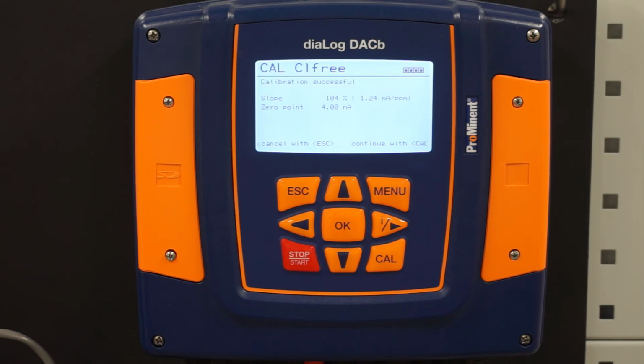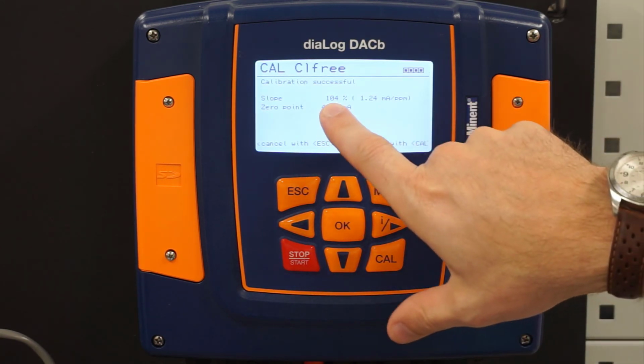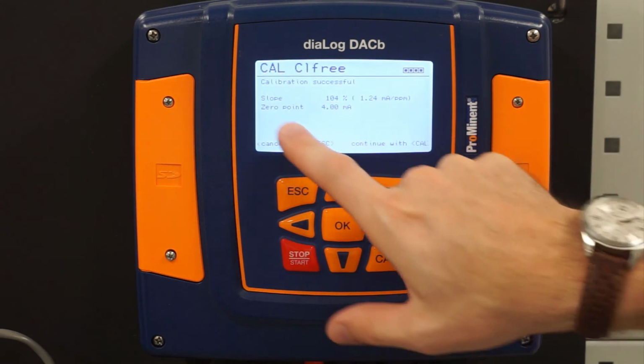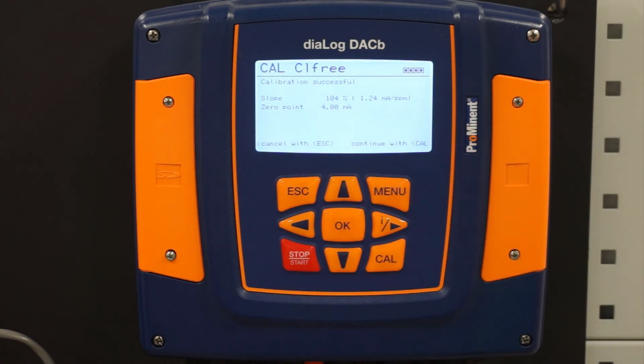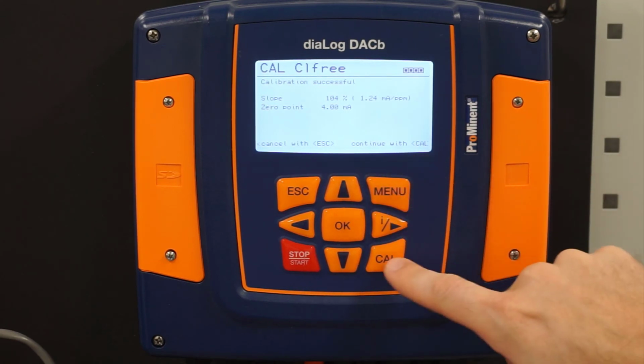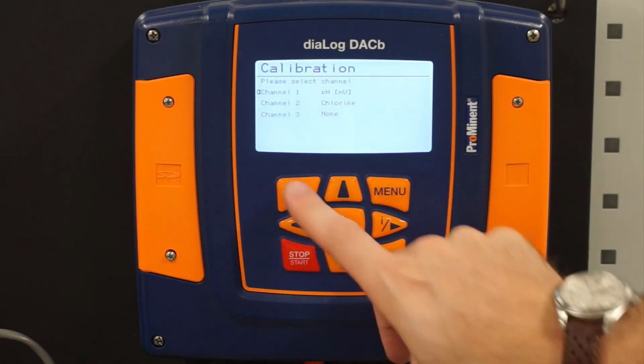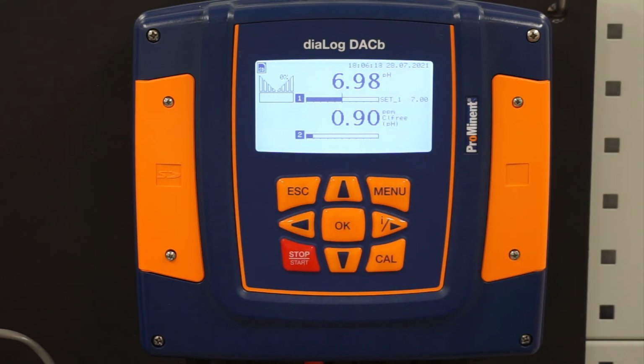If you have the stuff already on hand, you can wait till you get down to 20%. If you need to order it, I would maybe order it at 30%, and then you would have it on hand to change it. Because if I get below 20, it's going to tell me my calibration is invalid. I'm going to continue with calibrate, and at that point, my pH and my chlorine are both calibrated, and my system is up and running.